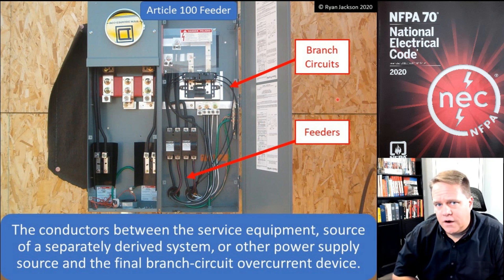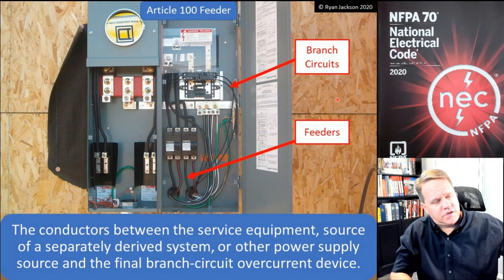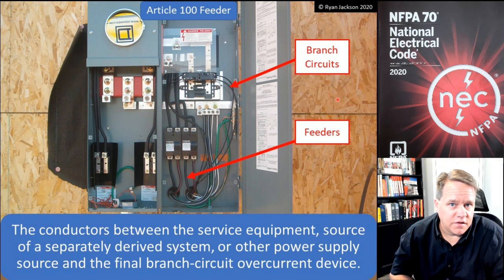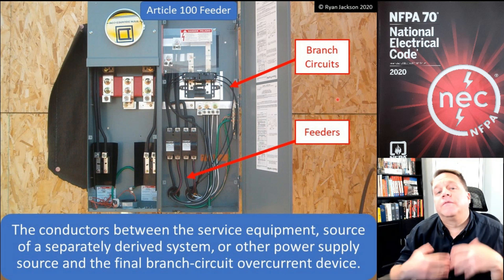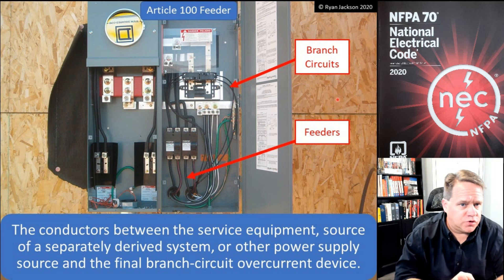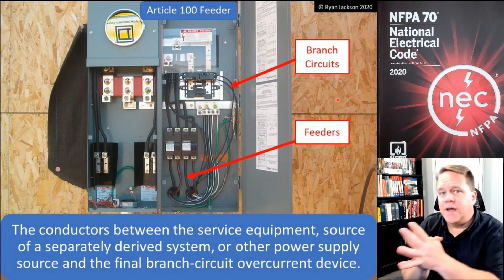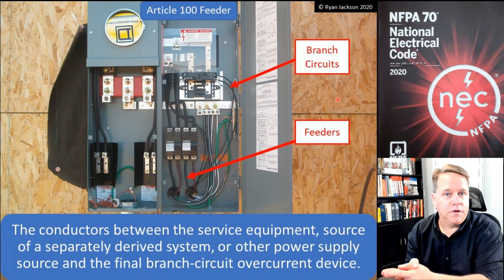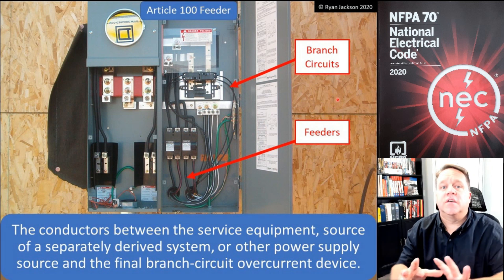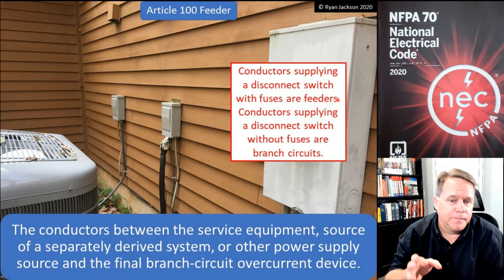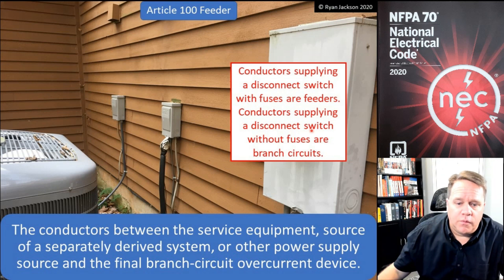A branch circuit starts at the last breaker or fuse and ends at the utilization equipment. Everything between the service disconnect and the branch circuit overcurrent devices is a feeder circuit. So a feeder circuit usually starts at a breaker or fuse and ends at a breaker or fuse — that's how it typically works.